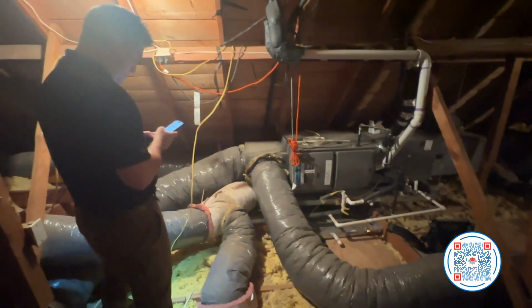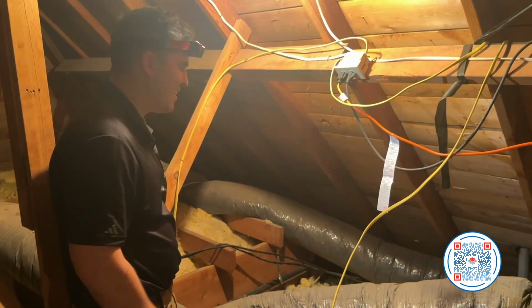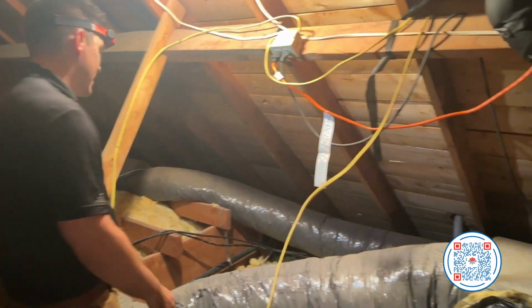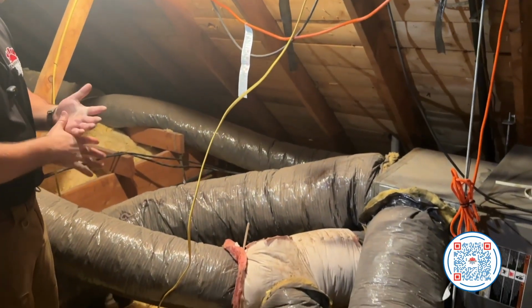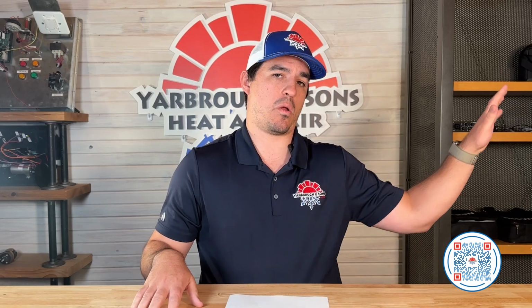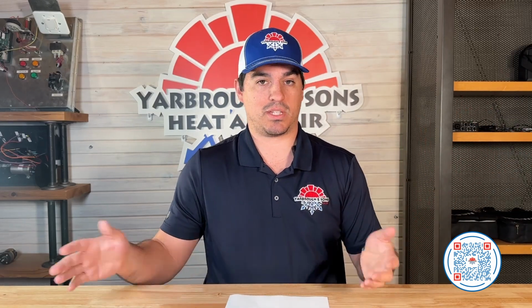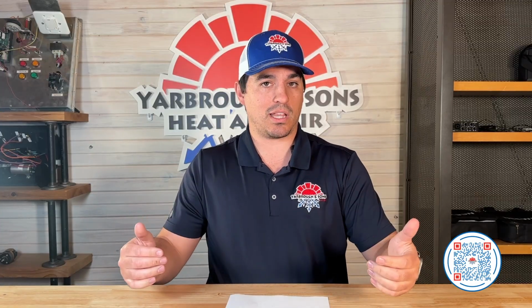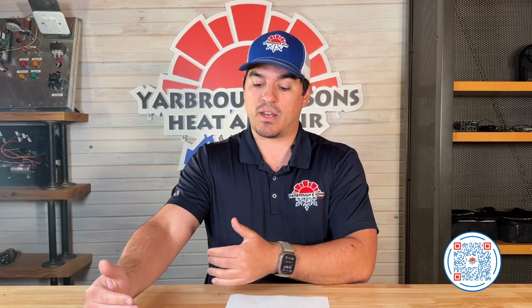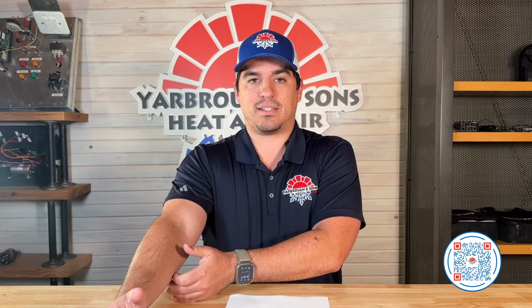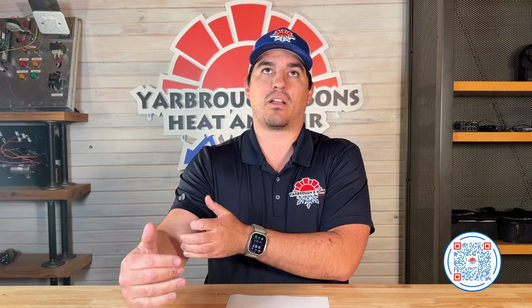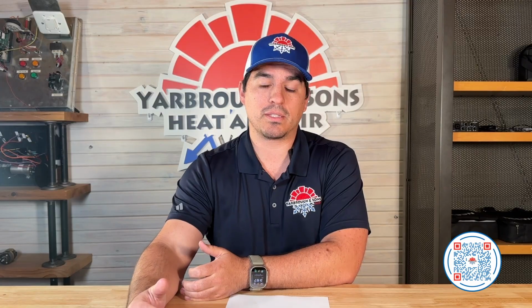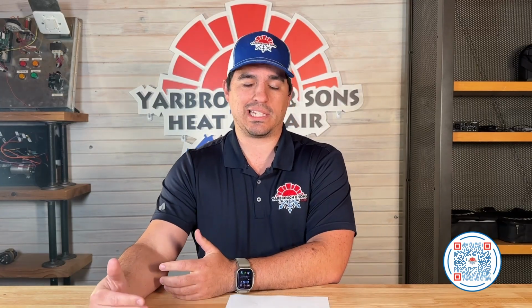Other things to be aware of: make sure ductwork is designed appropriately for that system. Systems back in the day didn't really care about static pressure, but systems today care a lot about it, working hard to meet the efficiency levels the EPA requires. Because they can push a lot of air, it can cause higher strain on components, so your ductwork needs to be adequately sized for that variable capacity system.